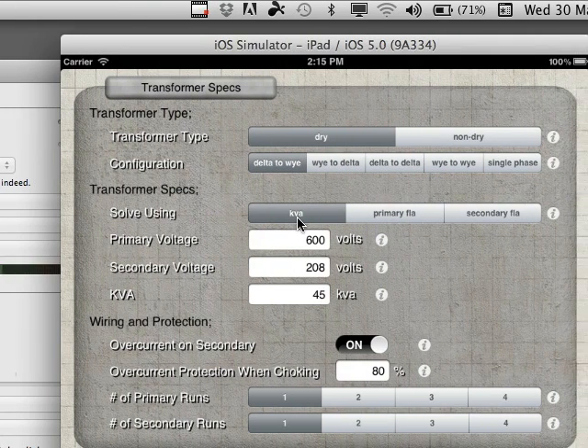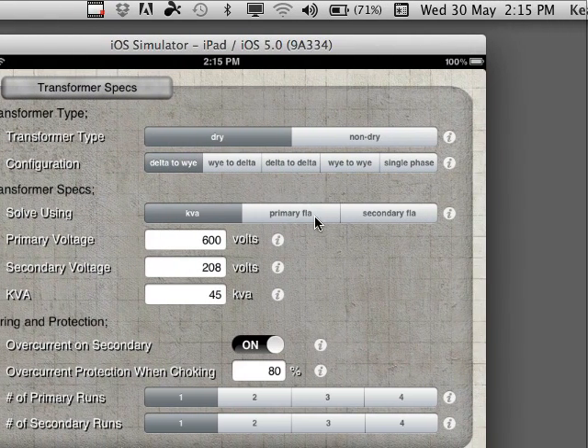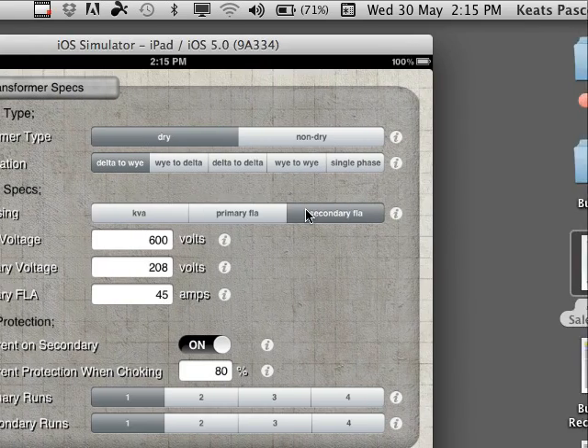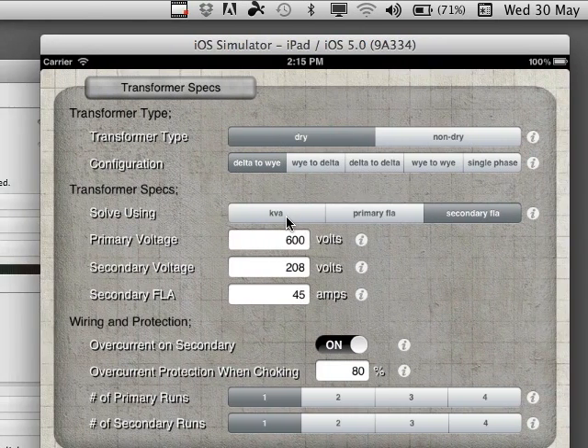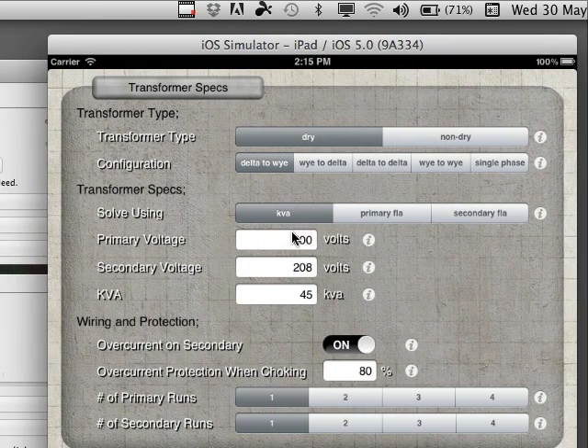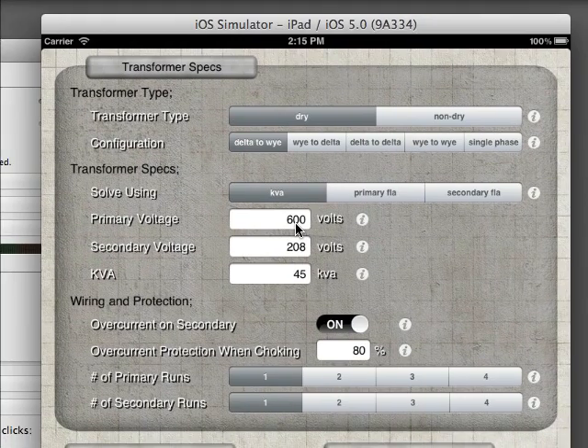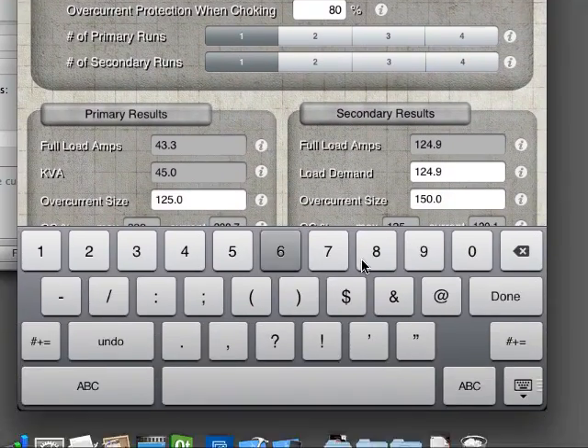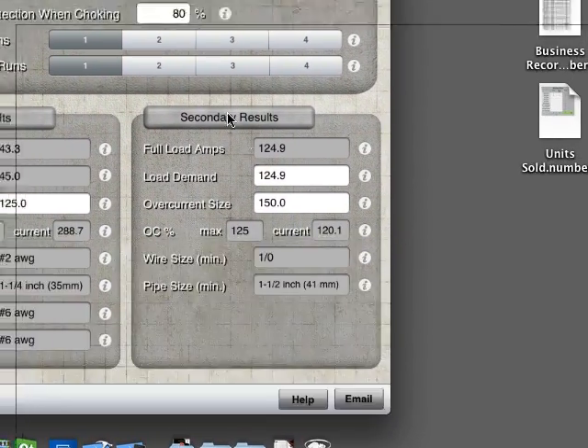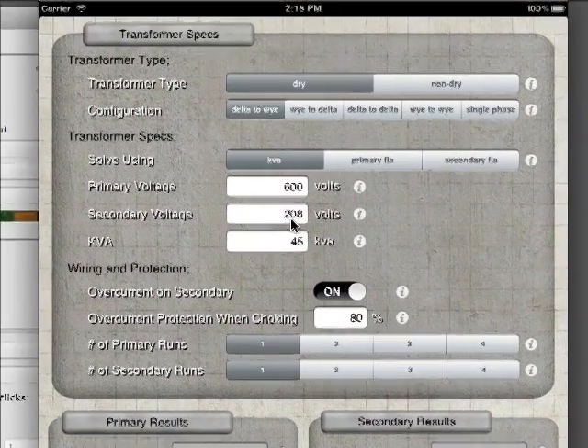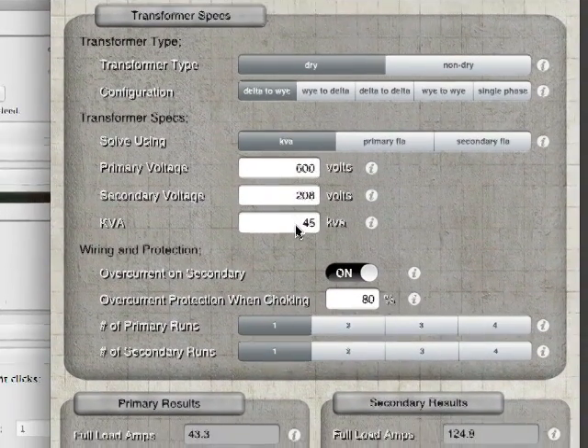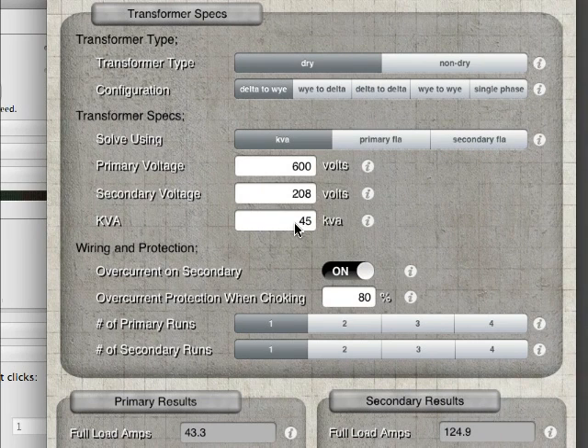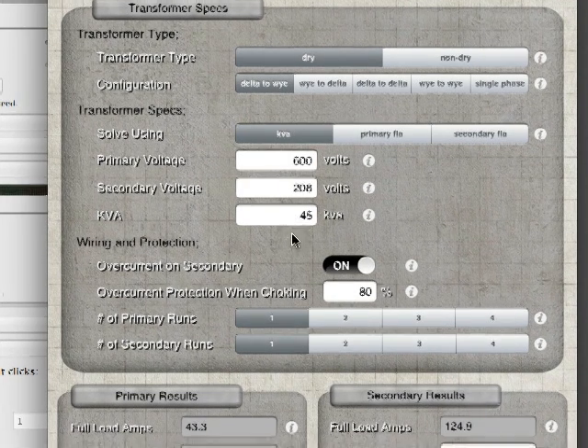You can solve by KVA, or solve by primary FLA or secondary FLA. So if you know your load, today we'll go to KVA, put in your primary voltage, we'll keep it 600. You put in your secondary voltage, which we'll keep it 208 for today, KVA, we'll keep it 45, supports any numbers here, decimals, whatever.